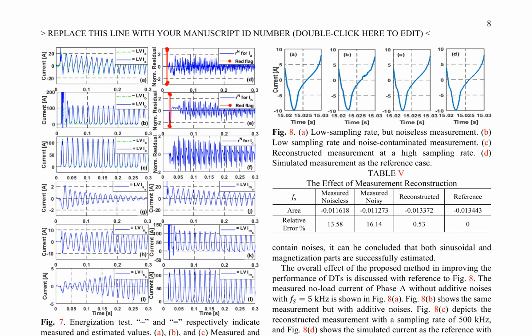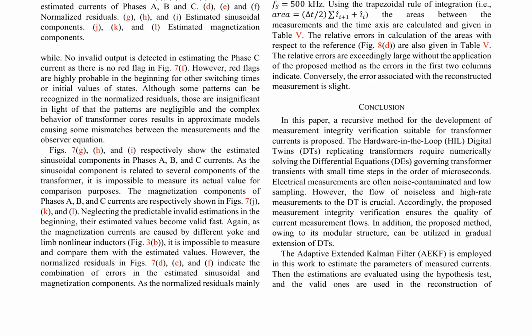these estimations using hypothesis tests. Valid estimations are then used in the reconstruction of measurements, significantly improving the performance of DTs. The paper presents several tests to validate the proposed method, including an inrush test and an underload switching test. The results show that the proposed method is capable of tracking currents, even in the presence of noise and nonlinearity.